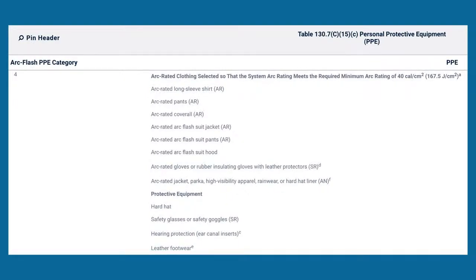Now, I'm going to state something here, and people are not going to like what I say, but I'm telling you, you can do this. All right? Now, that never happens. There was this thing going around at one time, and they said you can never work on anything over 40 cal. 70E does not tell you that. The 40 cal where people were making this assumption was based on the hazard risk category with a lot of conservative values built in. But nowhere in 70E does it say I can't work over 40 cal. As a matter of fact, I've seen 100 cal suits. All right? And the reason is because sometimes they have to do it. I would not do it.